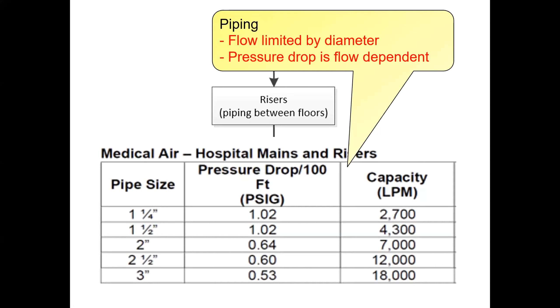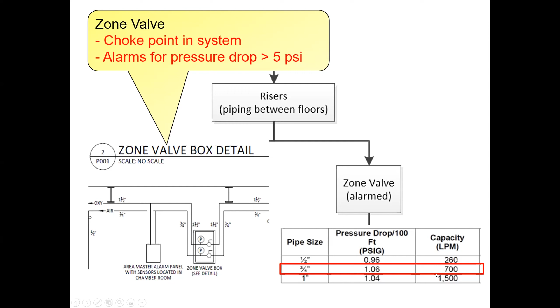And again, this is just a little clip out of what a blueprint might look like. And these are alarmed, as I said, for air and oxygen. And if you draw too much flow from them, the pressure drop will cause an alarm. And you need to know what size the pipe fitting is so that you can know what the capacity is, the maximum capacity at an assumed pressure drop. In this case, we assumed 1 PSI. And then what do you do? Well, you've got to have a spreadsheet and the calculations.